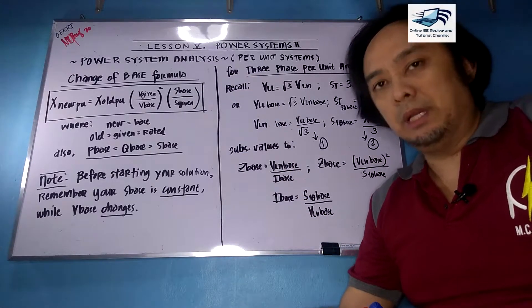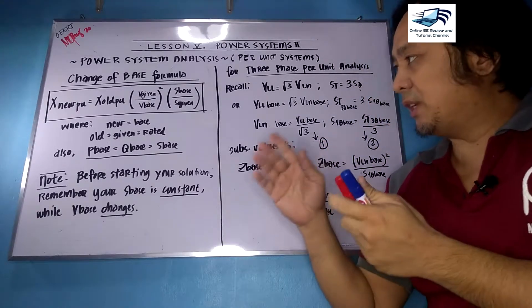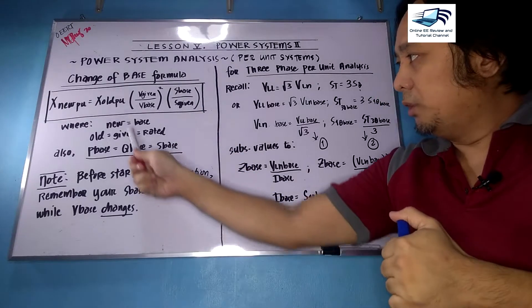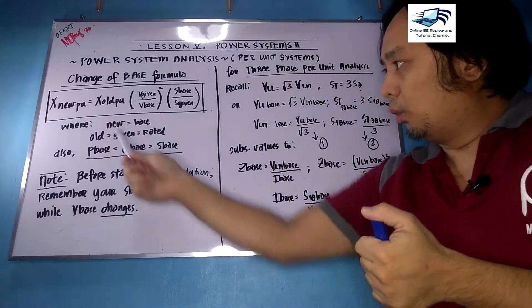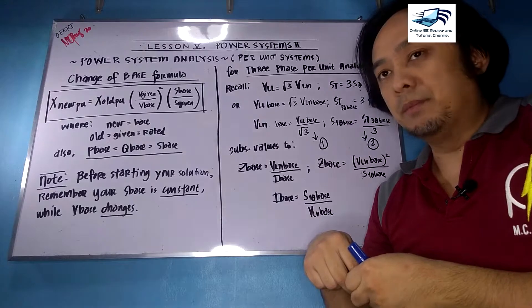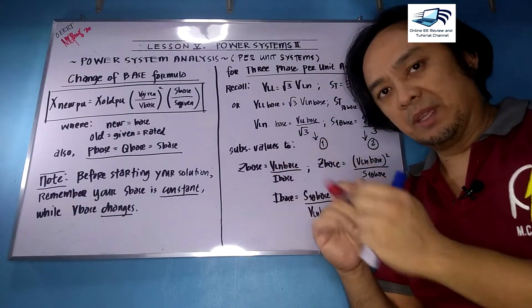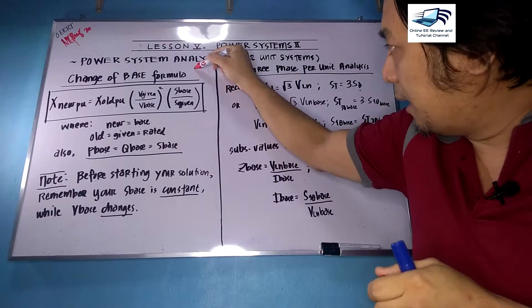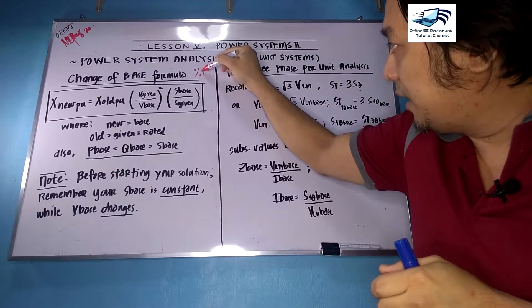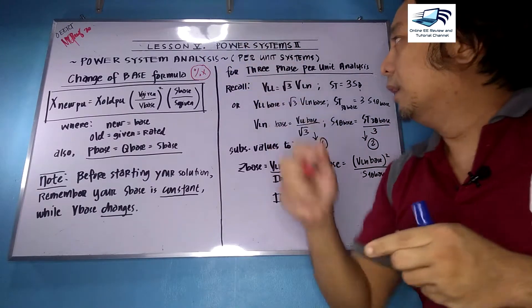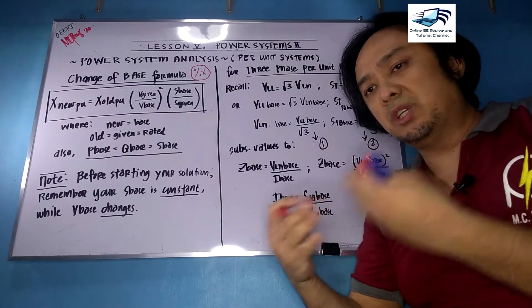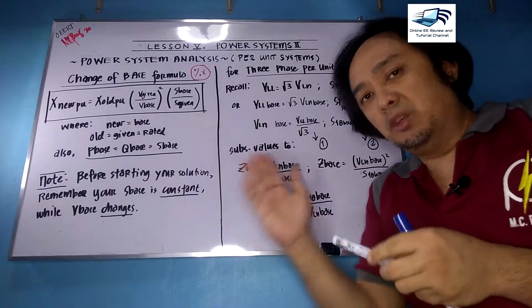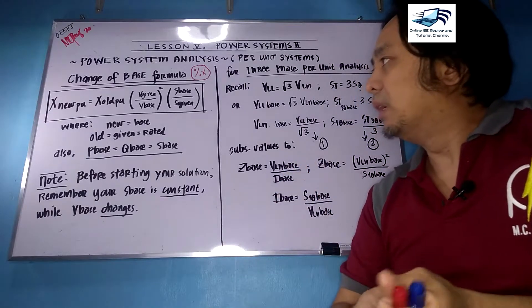Moving forward to the change of base formula — when you say 'base,' there is a synonym I incorporated on this slide: 'new' equals 'base,' that is the new value; 'given' equals 'rated.' These are synonyms with the same definition. When you have the change of base formula, you always apply it on the percentage reactances of your generators, transformers, or even loads.